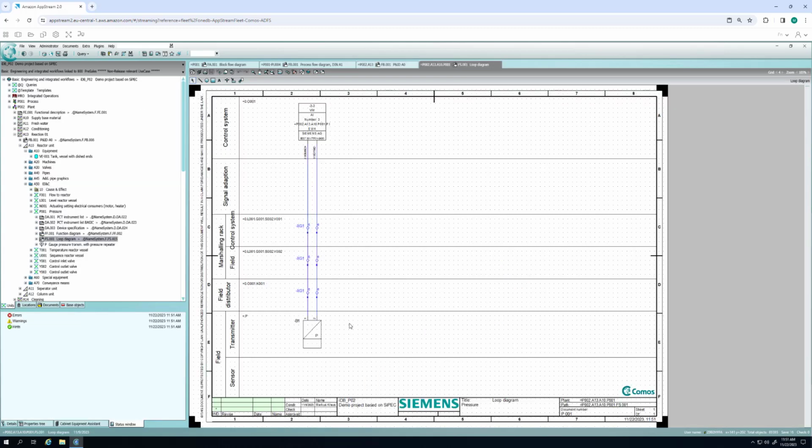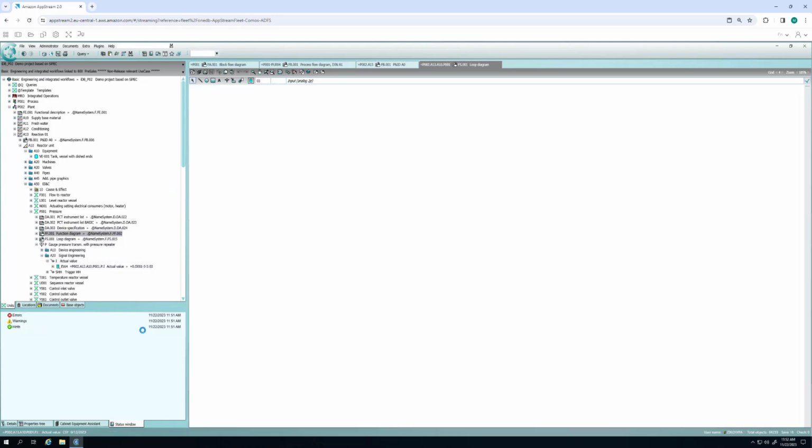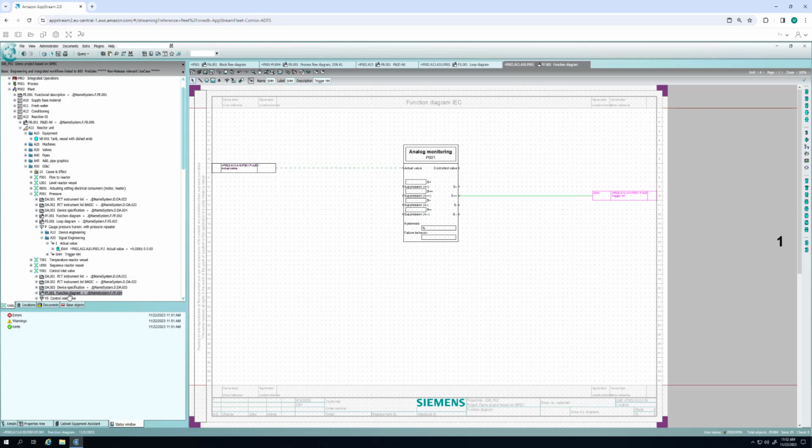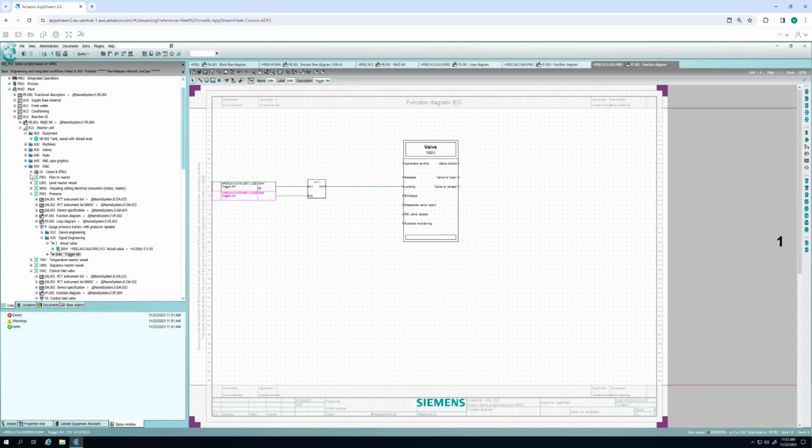Instrumentation-wise, we have got the loop where we find sensor elements with the technical data up to the needed I/O, which takes in this 4 to 20 milliampere signal. The signal can already be used here on logical diagrams that explain the basic automation concept behind it, and give already the information that the signal high should interlock the inlet valve.